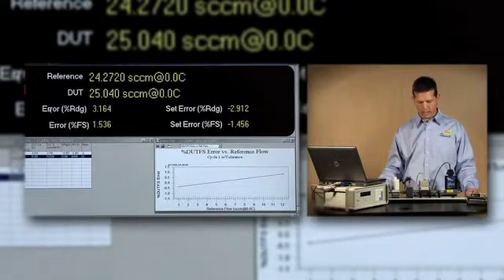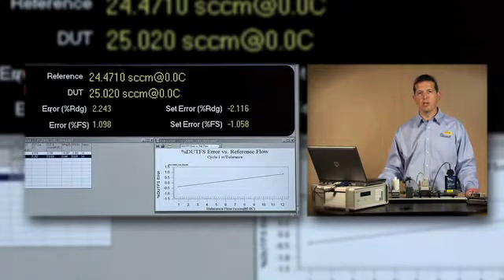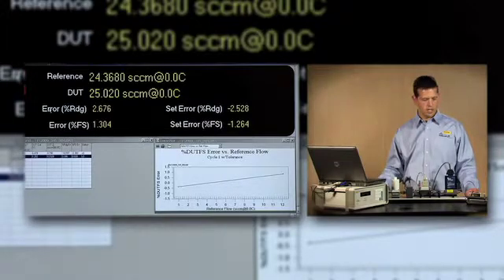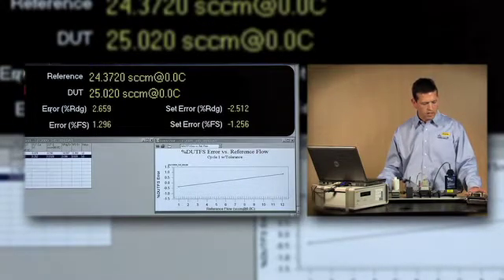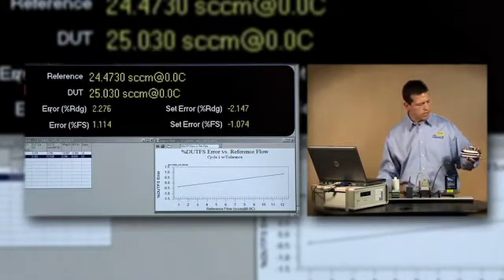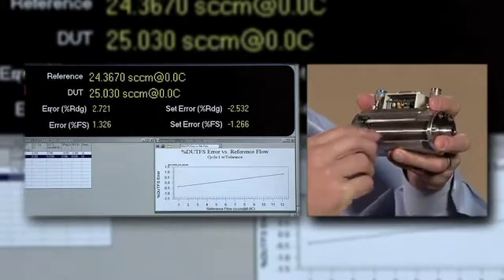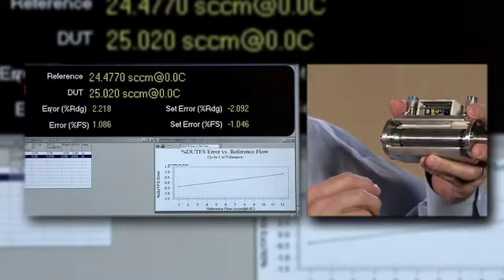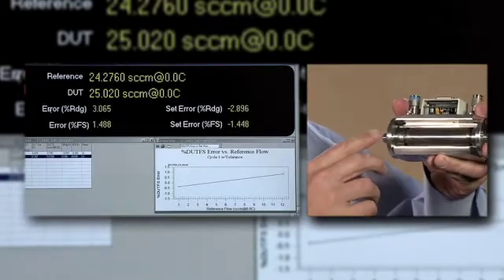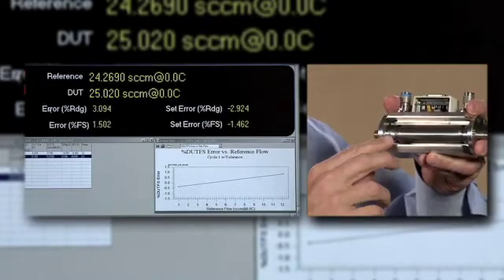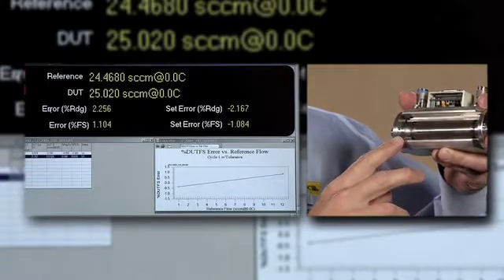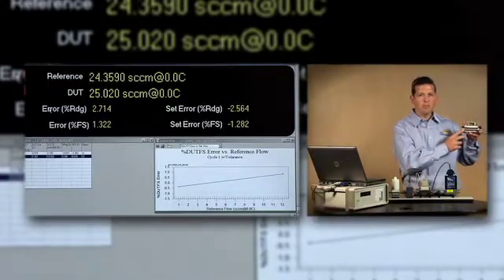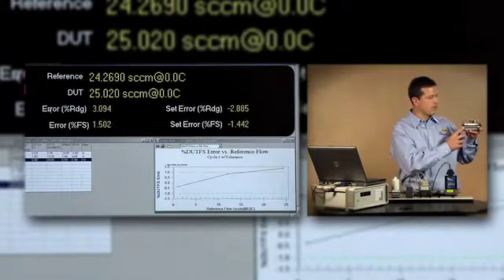Now our Molbloc here is a laminar flow element type Molbloc, or a Molbloc-L. Our laminar flow elements in the Molbloc/Molbox system are unique in that they use a patented design that includes a thin flow path for the gas to travel through the Molbloc, which is defined in this case by a piston and cylinder. So you have a very small annular space that produces up to a 50 kPa or almost 7 psi pressure drop, which is much larger than typical.